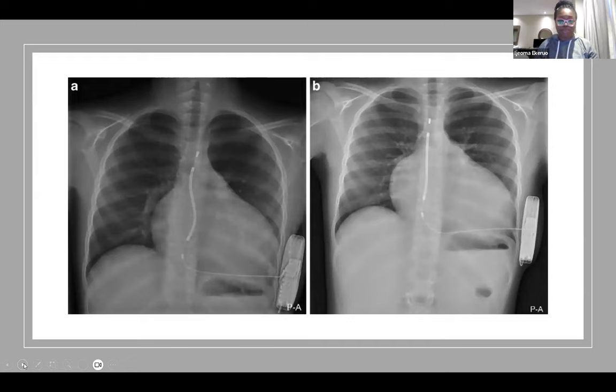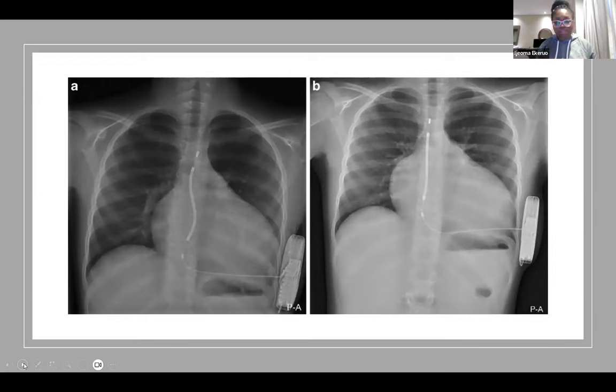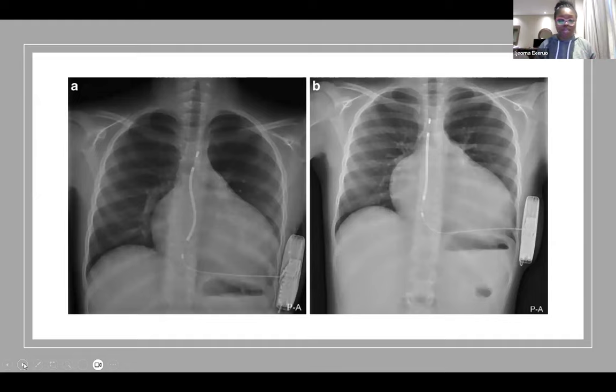One device you may encounter is the subcutaneous ICD — it's extra-thoracic, meaning the lead and device are underneath the skin but over the rib cage. Because of this, it's a bigger device, and the shock can go up to 85 joules compared to 40 joules from an internal device. It has no pacing capabilities — it can temporarily pace post-shock, but it cannot painlessly pace you out of any arrhythmia.